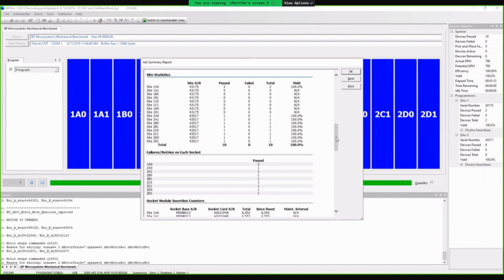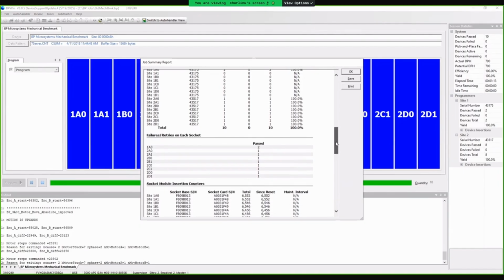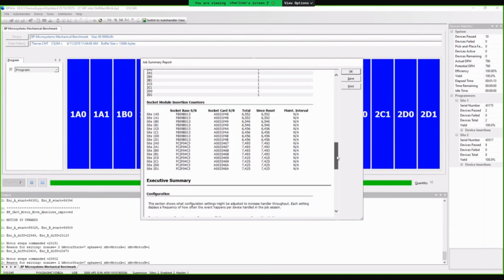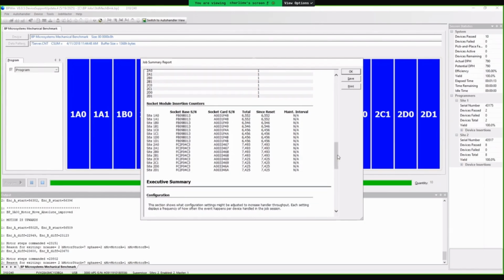As for socket wear, if you scroll down a little further, we have the socket module insertion counters. Here you get the total number of insertions recorded. Once you've reached the max for the socket, which our average is 10,000, you can replace the sockets and reset the insertions for the new socket. You can even set up maintenance intervals.